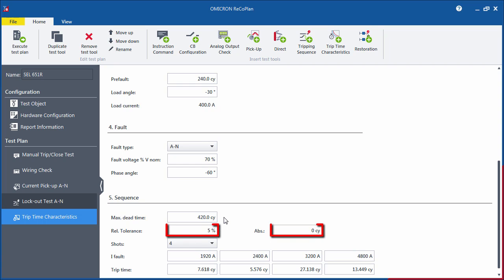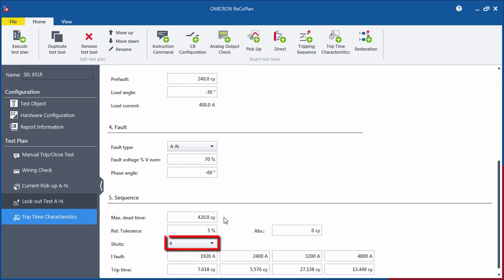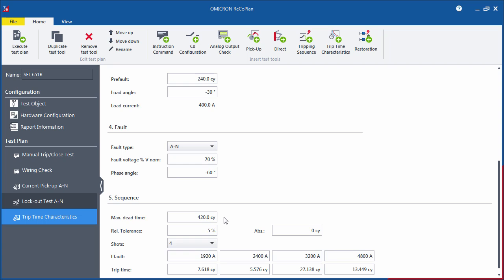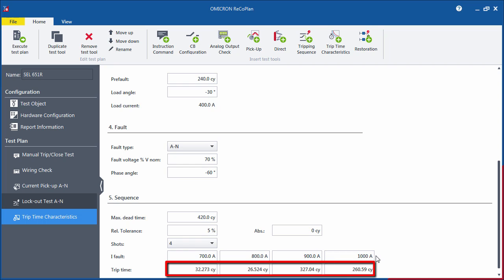Use the Tolerance fields to specify the permitted relative and absolute tolerances for the characteristic. Now, select the total number of shots and specify the fault current for each shot. You can enter as many cycles as the recloser control is programmed to lockout.